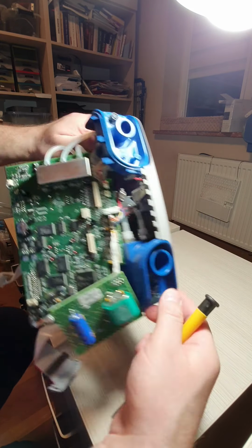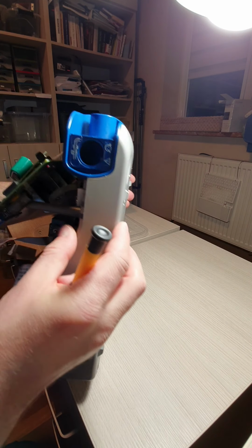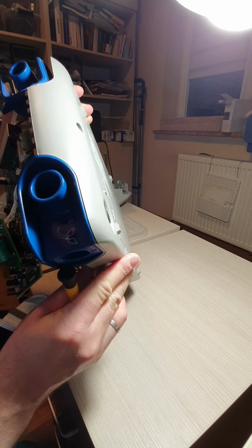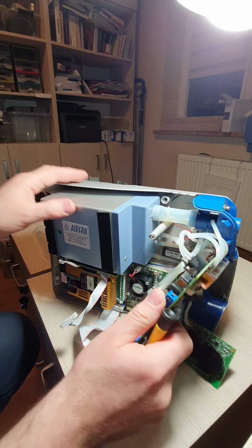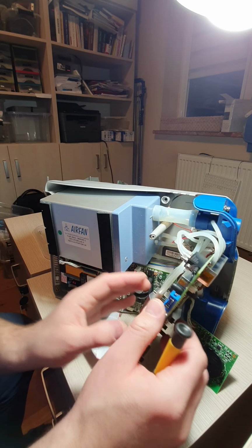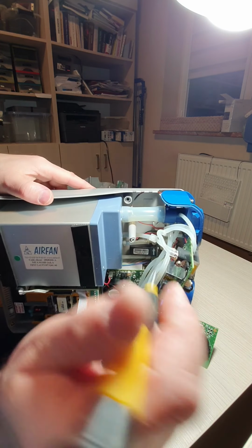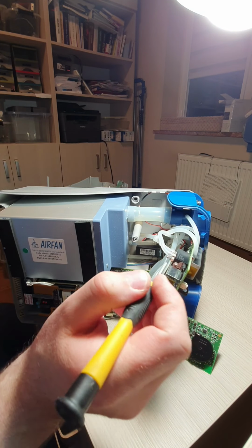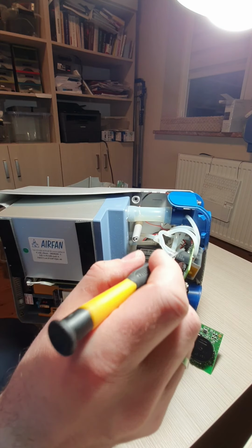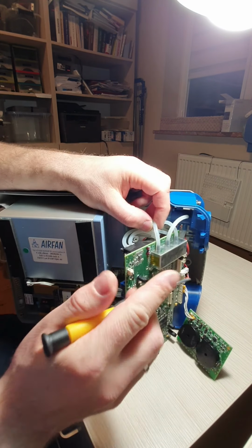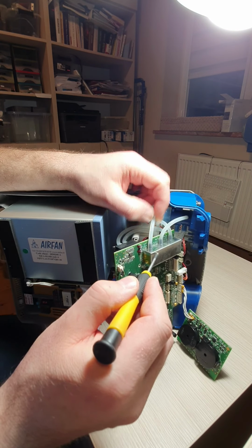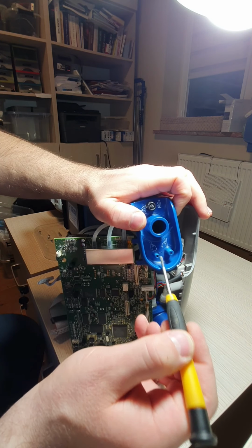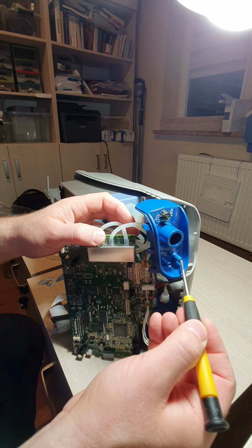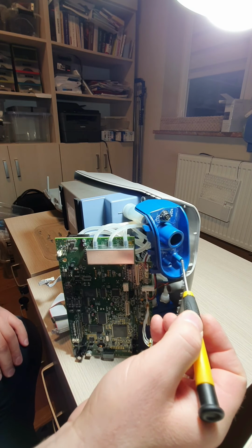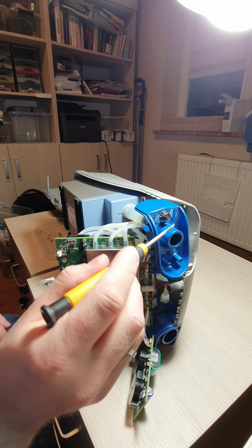It's a similar flow sensor at the exhalation port. There's also some diaphragm, probably, or something like this, which simply makes sure that the sum of the flow goes through the sensors. And this tiny valve, it's a proportional valve. It's the exhalation proportional valve, and depending on how much current is passing through the coil, it passes more or less air. The air pressure is measured by this air pressure sensor, and the output goes to this terminal, to this tube, which goes to the external valve. This is the symbol like this. This sensor measures the pressure at the output before the exhalation valve to realize the PEEP function.